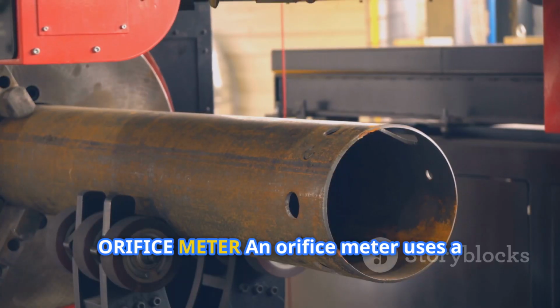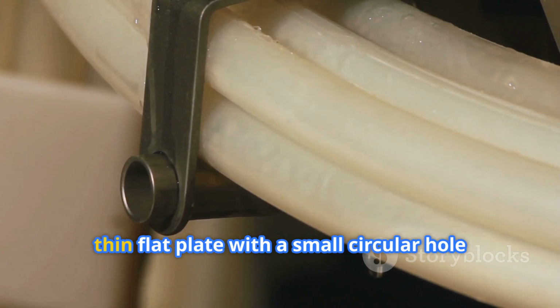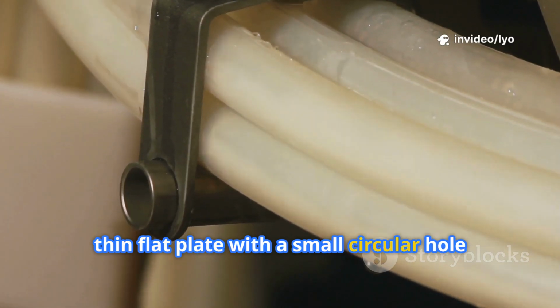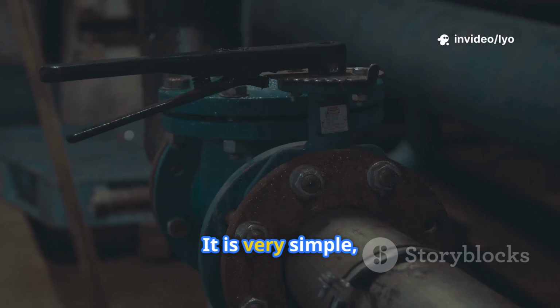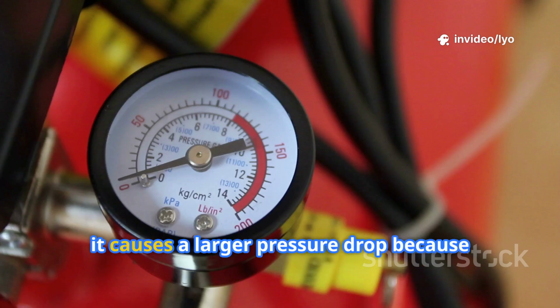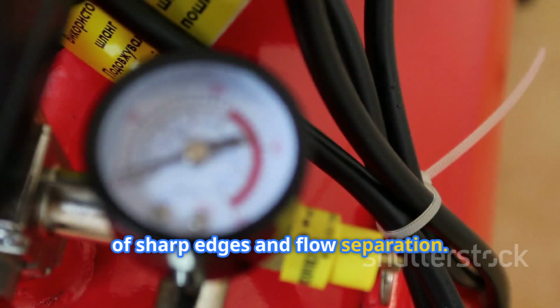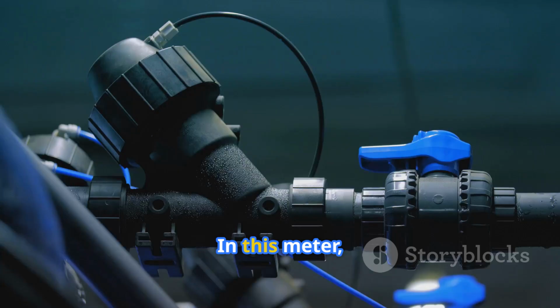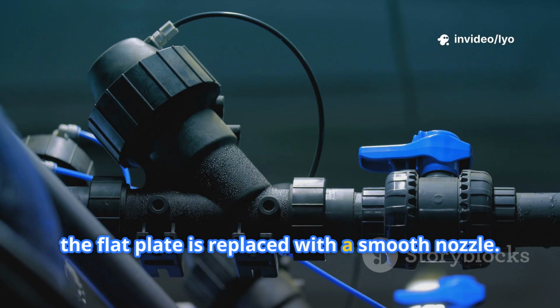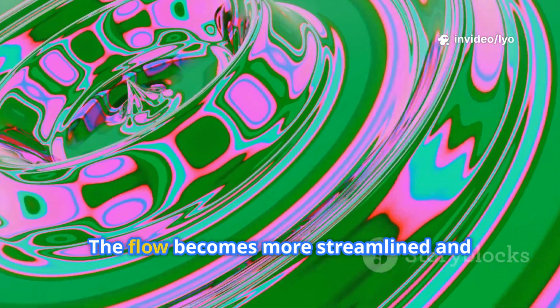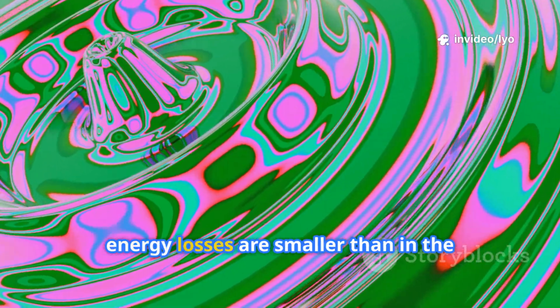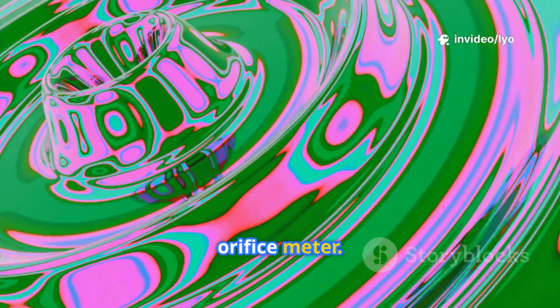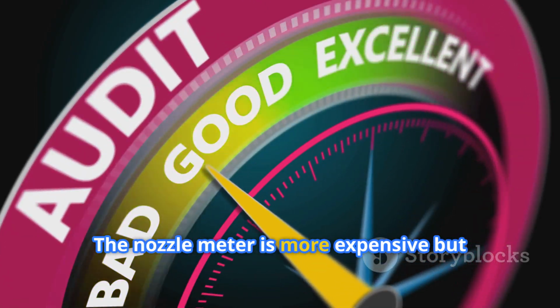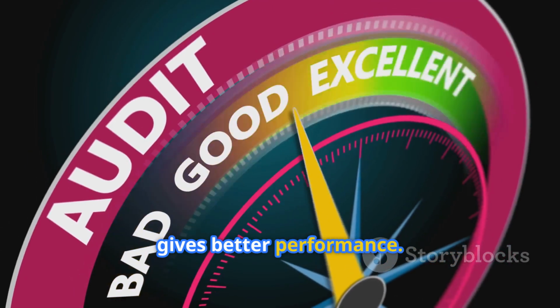Orifice meter. An orifice meter uses a thin, flat plate with a small circular hole in the center. It is very simple, cheap, and easy to install. However, it causes a larger pressure drop because of sharp edges and flow separation. Nozzle meter. In this meter, the flat plate is replaced with a smooth nozzle. The flow becomes more streamlined and energy losses are smaller than in the orifice meter. The nozzle meter is more expensive but gives better performance.